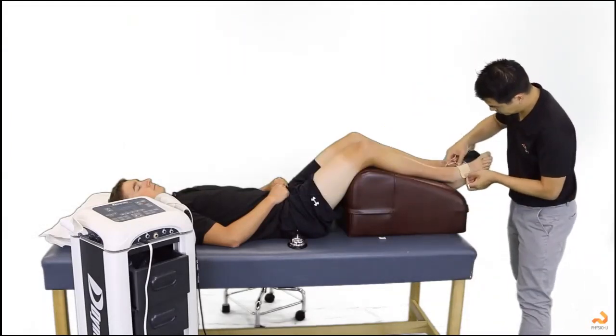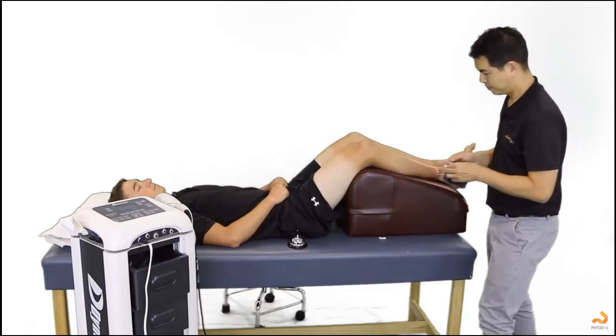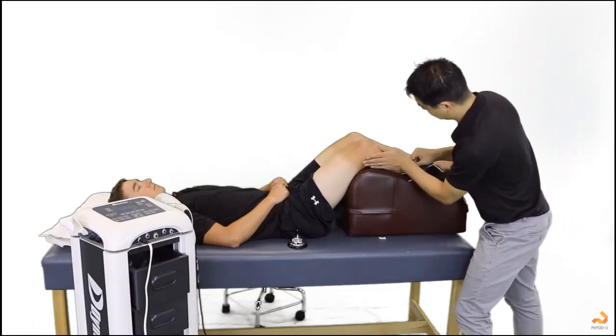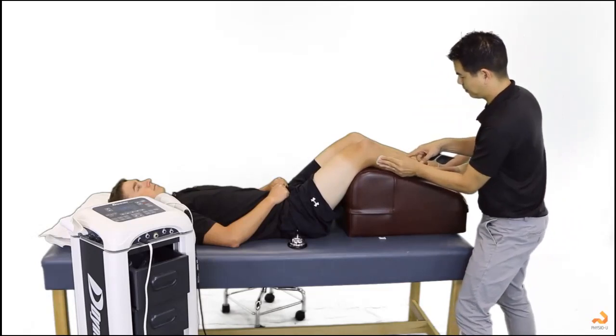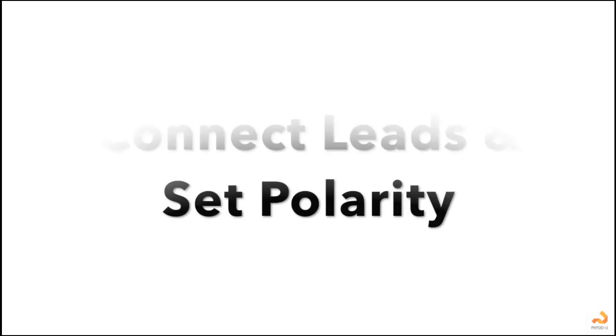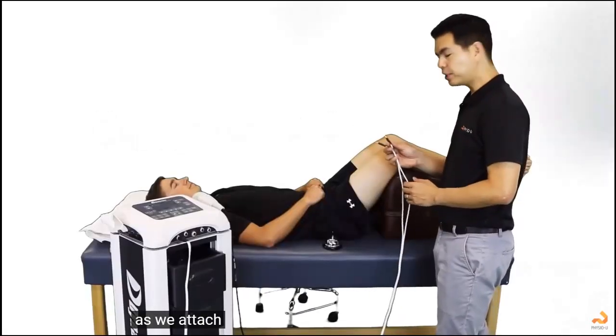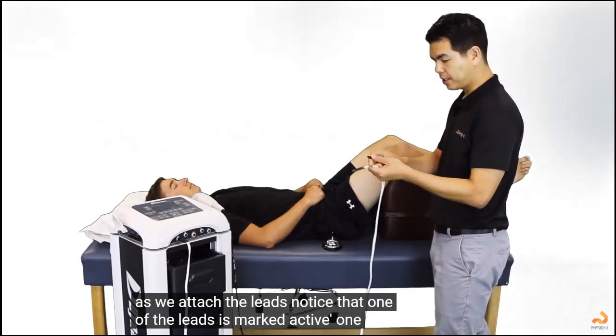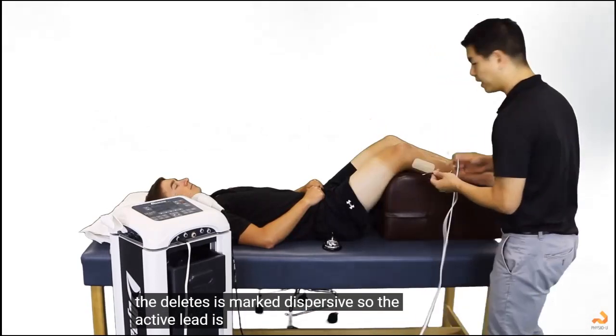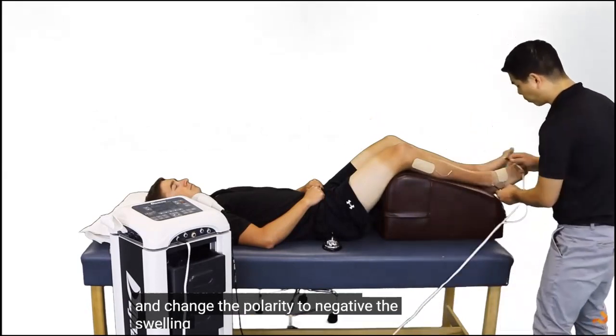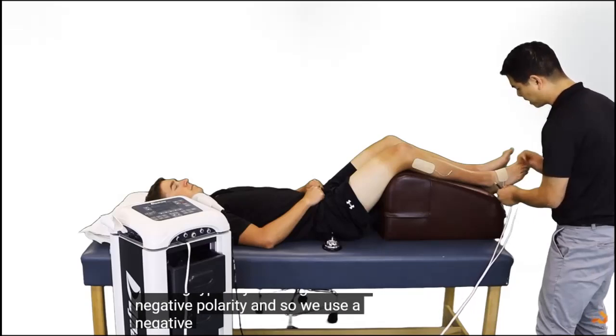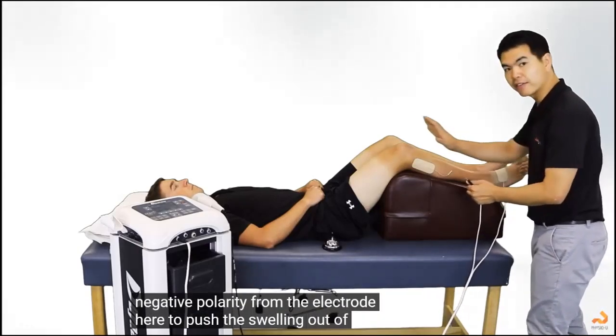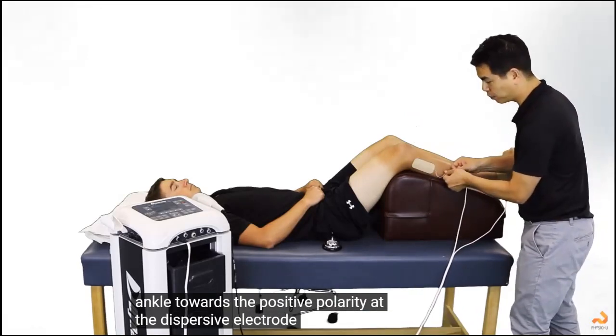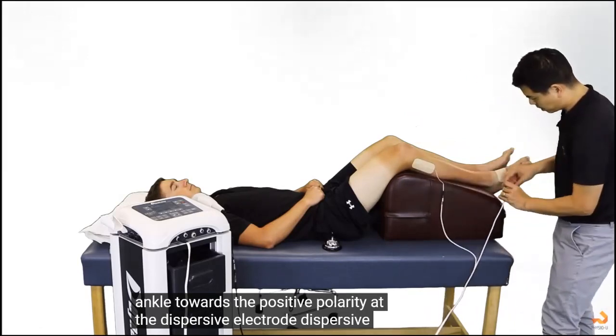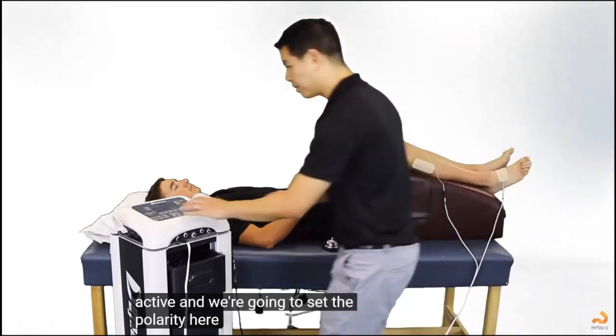Now we will apply the pads and connect the leads. As we attach the leads, notice that one of the leads is marked active, one of the leads is marked dispersive. So the active lead is the lead that I'll use and change the polarity to negative. The swelling typically is charged with a negative polarity, and so we'll use a negative polarity from the electrode here to push the swelling out of the ankle towards the positive polarity at the dispersive electrode. Dispersive, active, and we're going to set the polarity here to negative.